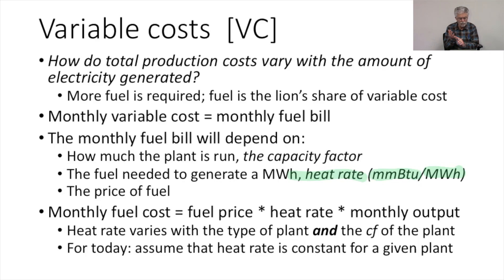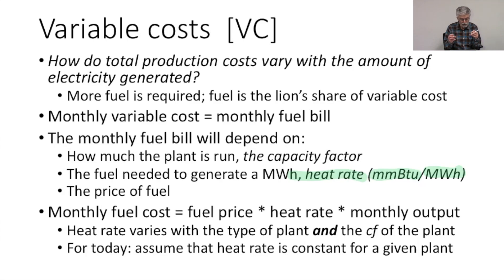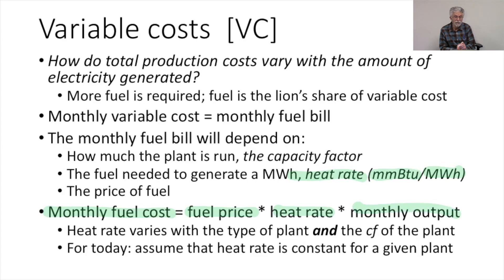So what do we have so far? The monthly fuel bill depends on how much we run the plant, how much fuel it takes to generate a megawatt hour of output, and the price of fuel. We're going to take those three things and use them to calculate our monthly fuel bill. The monthly fuel cost is just the fuel price times the heat rate times the monthly output in terms of megawatt hours.